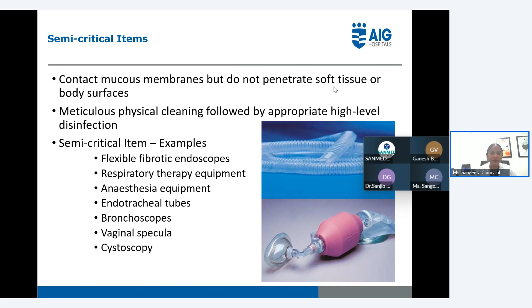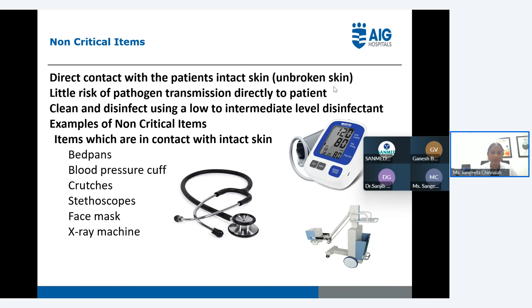Non-critical items have direct contact only with intact skin. They are not inside the body and not on the mucous membrane; they are on the outside of the skin. So there is little risk of pathogen transmission directly to the patient. Clean and disinfect them using a low or intermediate-level disinfectant like alcohol swabs or an alcohol-based solution. Examples are a blood pressure cuff, stethoscope, face mask, and X-ray machines.